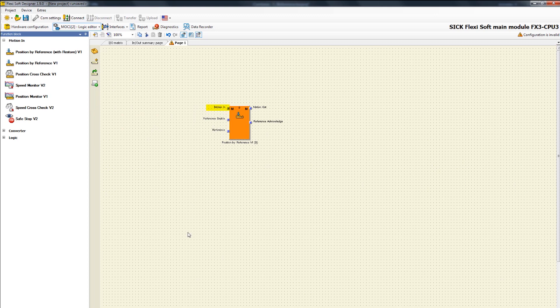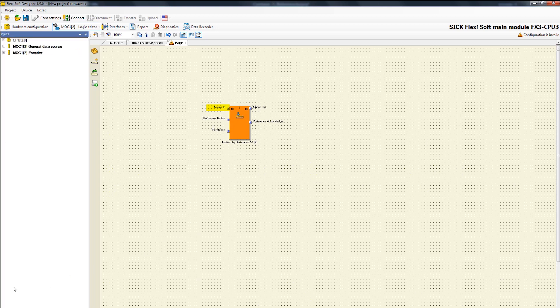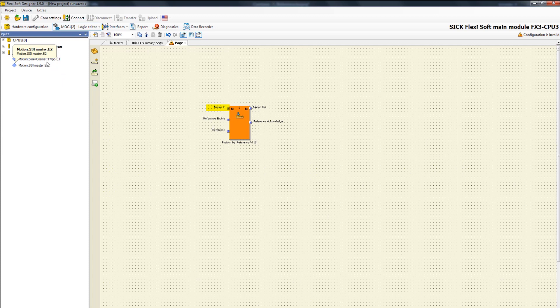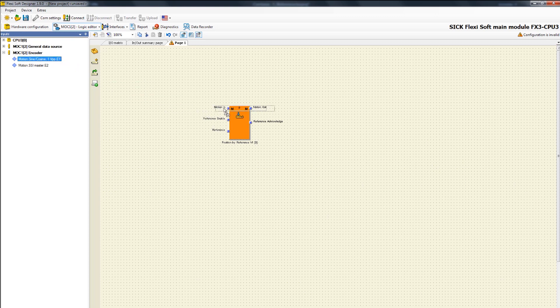The input motion in expects a relative position which comes from an encoder directly. You can find the encoder under inputs in the cluster MOC1 encoder. Because we want to produce an absolute position out of the sine-cosine encoder, we have to choose the sine-cosine encoder and place it in the configuration area.